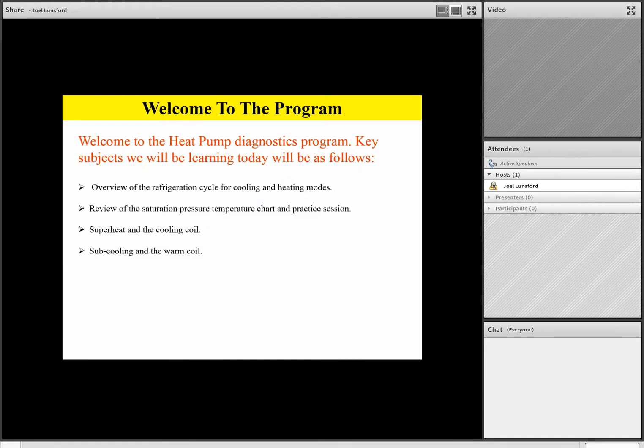We're going to be talking about some key things today as follows. We're going to overview the refrigeration cycle for cooling and heating modes of operation. We're going to review the saturation pressure temperature chart, and we'll have some practice session together. We'll talk about superheat and subcooling and the condition that they relate to, specifically superheat in the cooling coil and subcooling in the warm coil today.